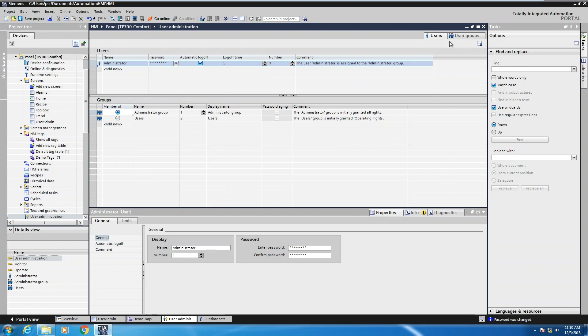In the upper right hand corner there are two tabs: users and groups. The users will belong to groups, and the groups will have authorizations assigned to them. So when you're logged in during runtime you have to be logged in as a user that belongs to a group that contains the authorization assigned to the object that you want to operate.